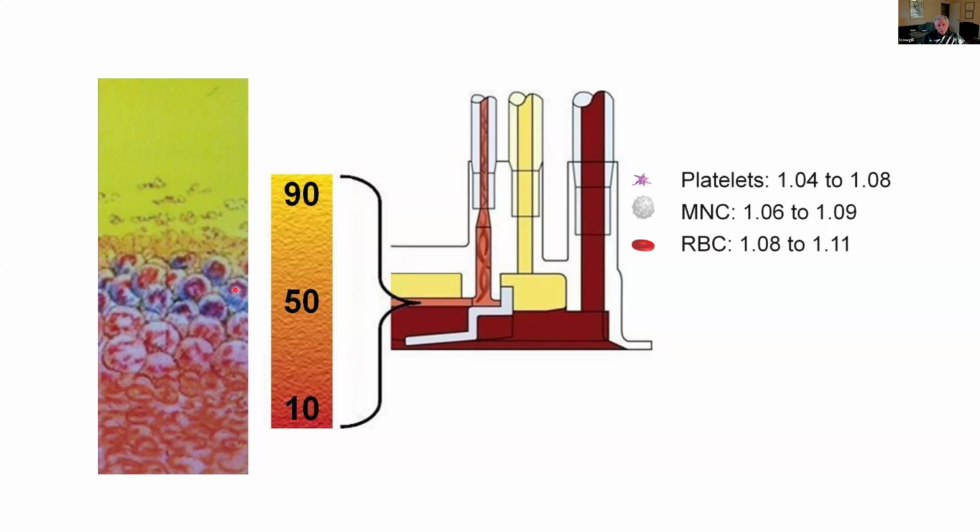And then as you get deeper and deeper into the layering here, the depth, then you collect different cell types. So these would be the lymphocytes. These maybe would be granulocytes, and then you get monocytes, eosinophils, and stem cells down here, and then you end up with the red cells at the very bottom. And you tell the machine to either collect high or to collect low by programming a parameter on the machine called the collection preference, which is just an arbitrary scale that tells the machine to collect from this layer, or this layer, or whatever layer.